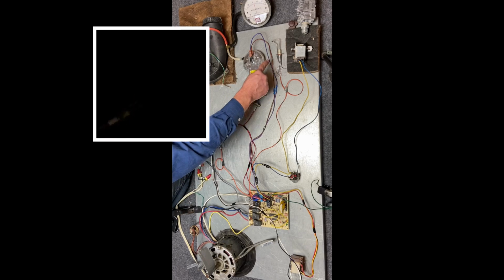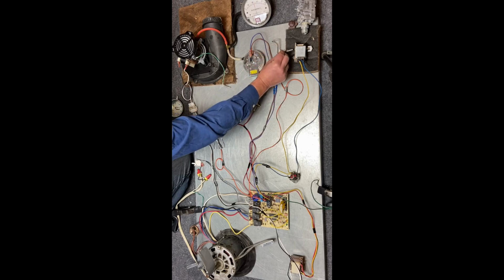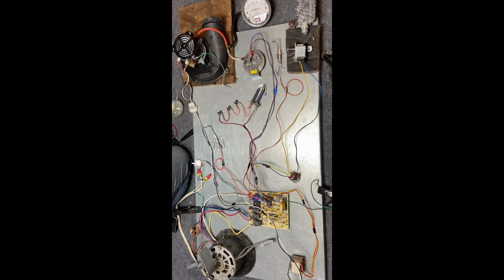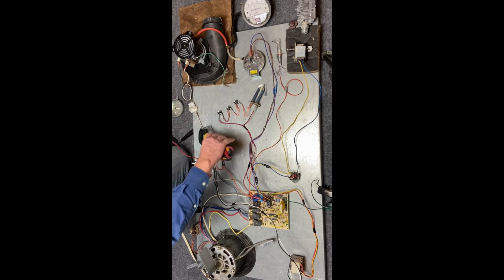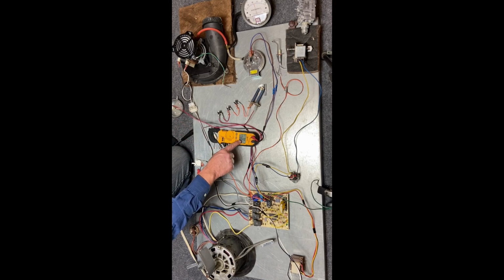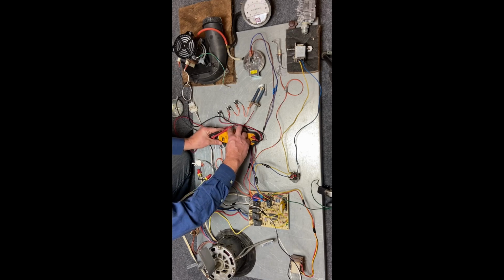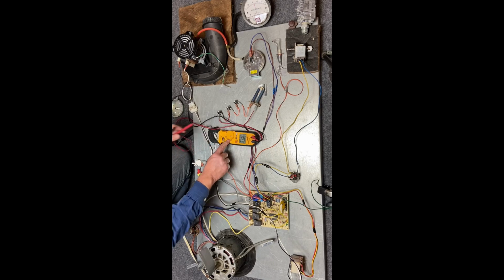A few seconds of no flame. We're going to end our spark, and that's going to pop right back out. So it said, hey, there's no flame. We go into a safety. Now I can check my voltage. The bottom number here is going to be voltage. I turn it to volts. The very bottom number down here is going to be voltage.